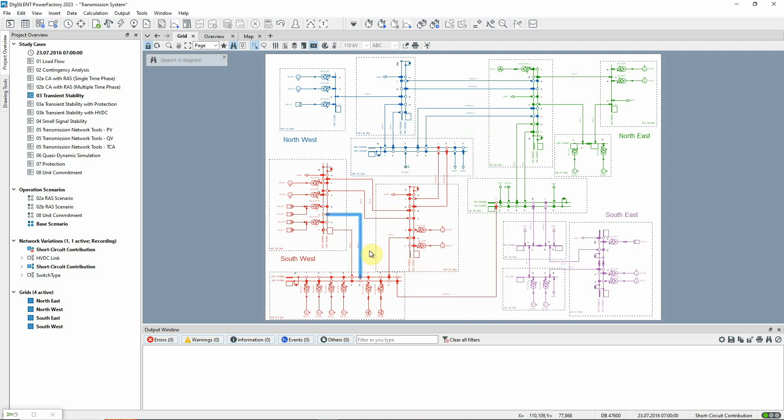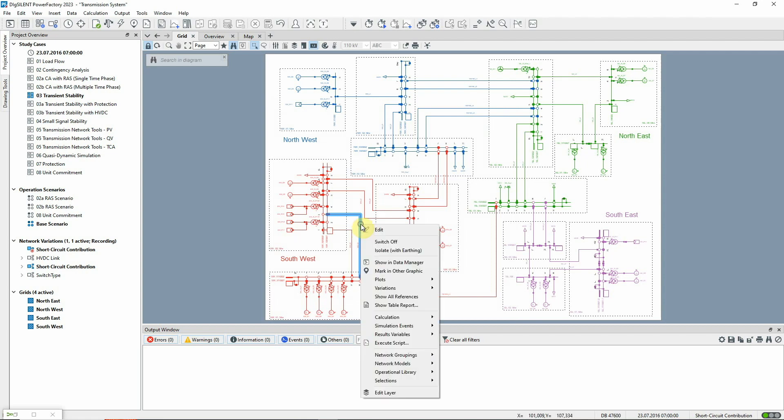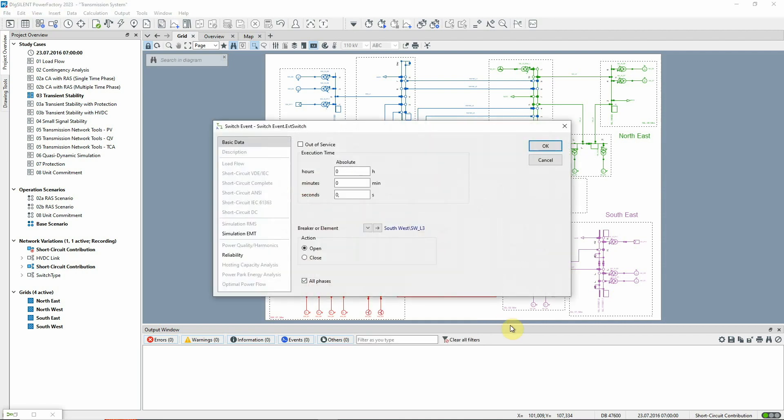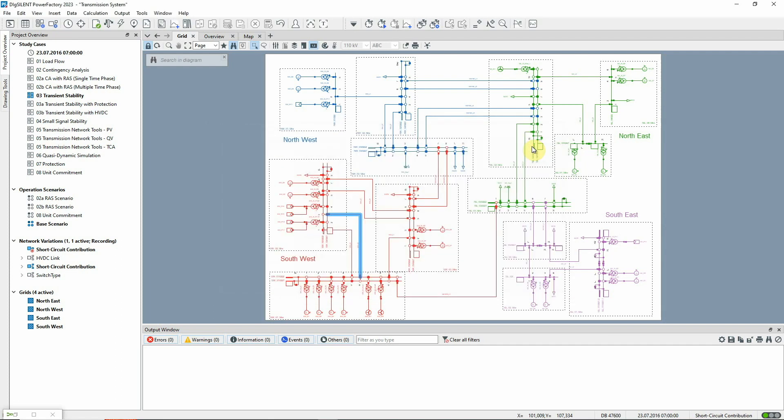Therefore, a second event is defined to open the circuit breakers at the ends of the line. Again, we right-click on the line, but this time define a switch event. We'll assume that the breakers will open after 100 milliseconds. The events are now set up.